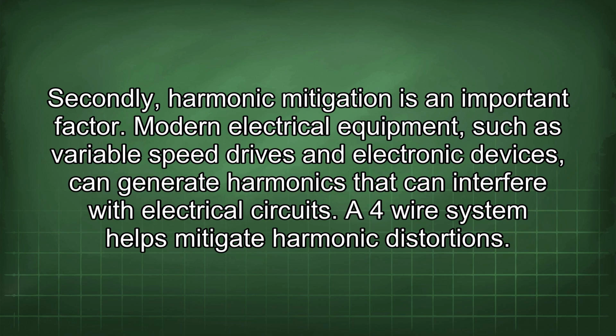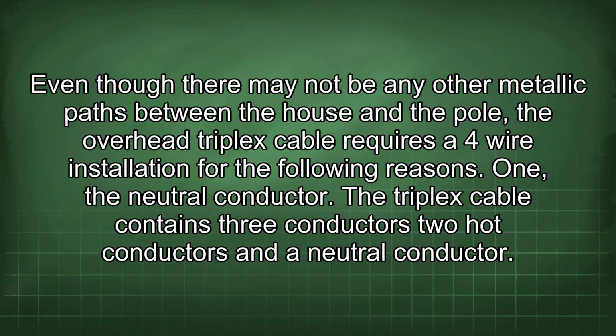Modern electrical equipment, such as variable speed drives and electronic devices, can generate harmonics that can interfere with electrical circuits. A 4-wire system helps mitigate harmonic distortion. Even though there may not be any other metallic paths between the house and the pole, the overhead triplex cable requires a 4-wire installation for the following reasons.